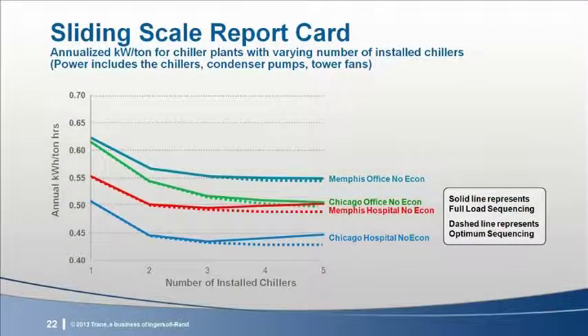Now, while we must normalize to get rid of the effect of ever-changing loads and come up with a metric, we must also create a better way of predicting what excellent performance is at a given site. Let's focus back in on the chiller plant for a moment and the report card. We need a sliding scale grading for chiller plants. I'm talking about guidance that accounts for the plant configuration and the load profile. A lot goes into the load profile.